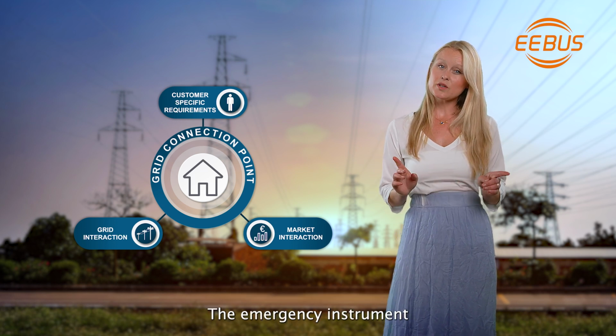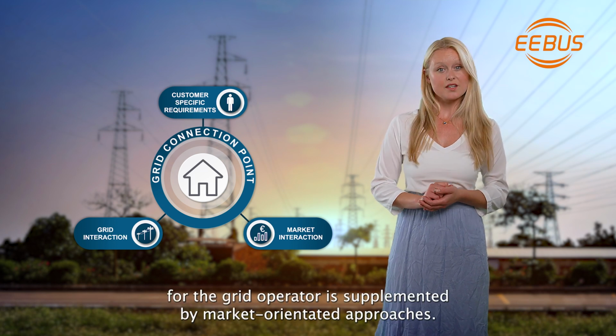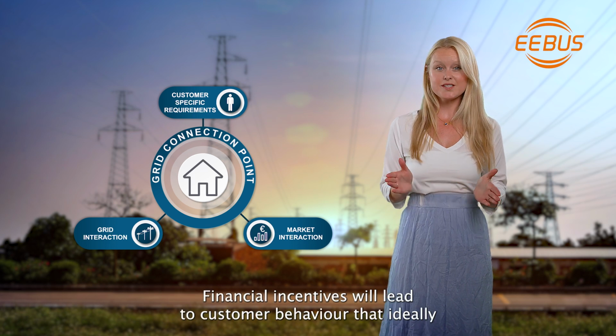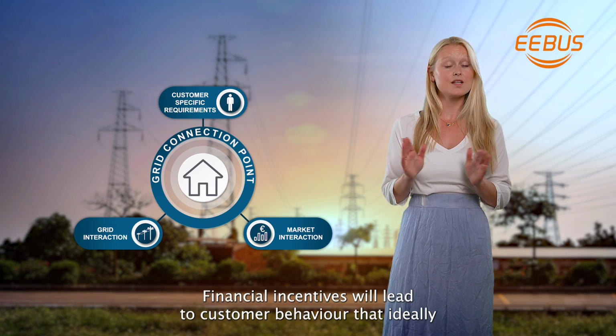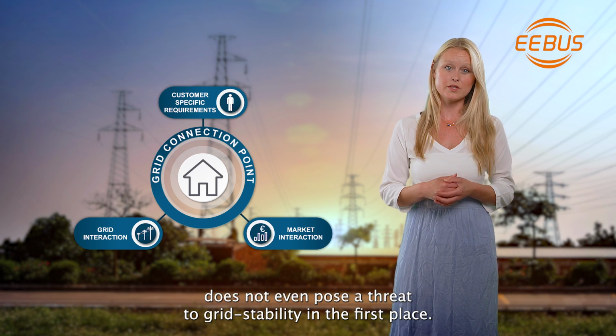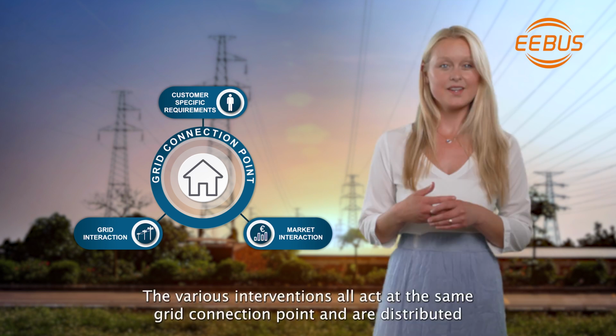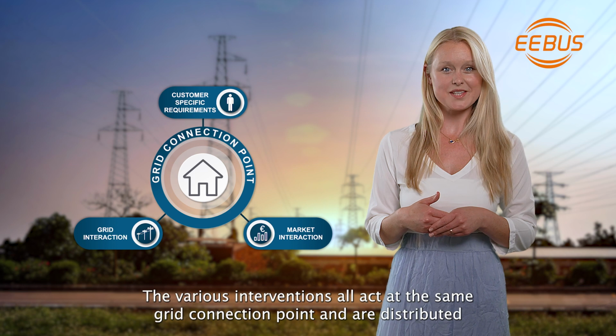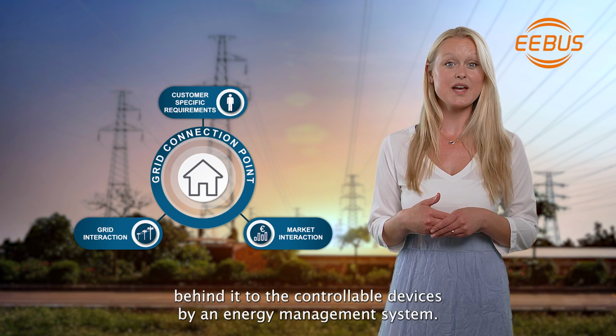The emergency instrument for the grid operator is supplemented by market-oriented approaches. Financial incentives will lead to customer behavior that ideally does not even pose a threat to grid stability in the first place. The various interventions all act at the same grid connection point and are distributed behind it to the controllable devices.